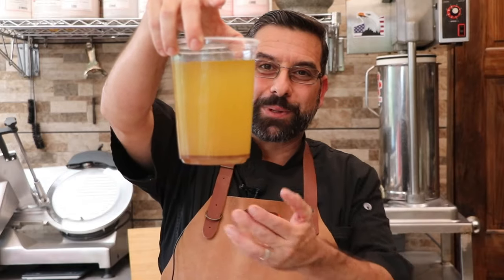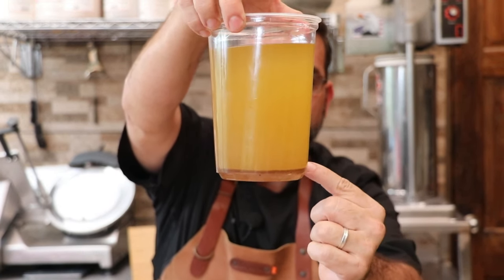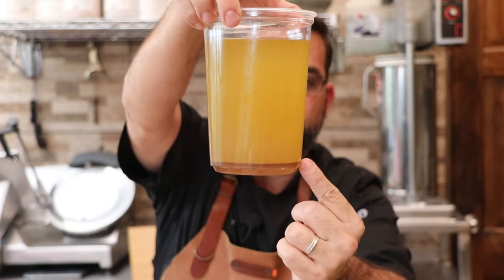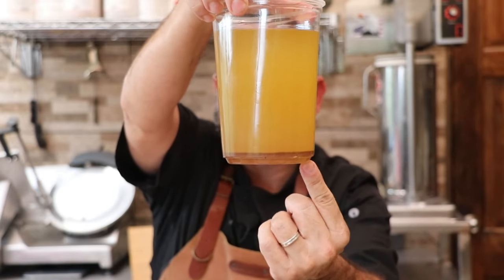Now I pulled the oil from it and this is what it looked like. Notice how it is incredibly cloudy. We've got a layer of debris that's accumulated here at the bottom. It's kind of fallen down. And then we've got a clear liquid. I don't know if that's showing up on camera, but we've got a clear liquid here at the bottom. That's actually water.